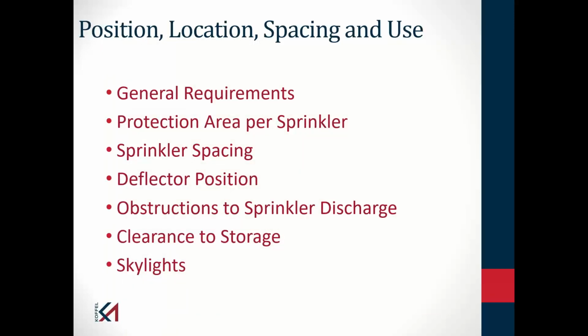Other installation requirements, and again, we could spend a couple of hours on these. I just want to go through the types of things that are covered by NFPA 13. Depending upon the type of sprinkler you have and the hazard that's being protected, NFPA 13 will establish the protection area, that this sprinkler is able to protect an area of 100 square feet or 130 square feet or 225 square feet. Those are common numbers that you will find in the standard.